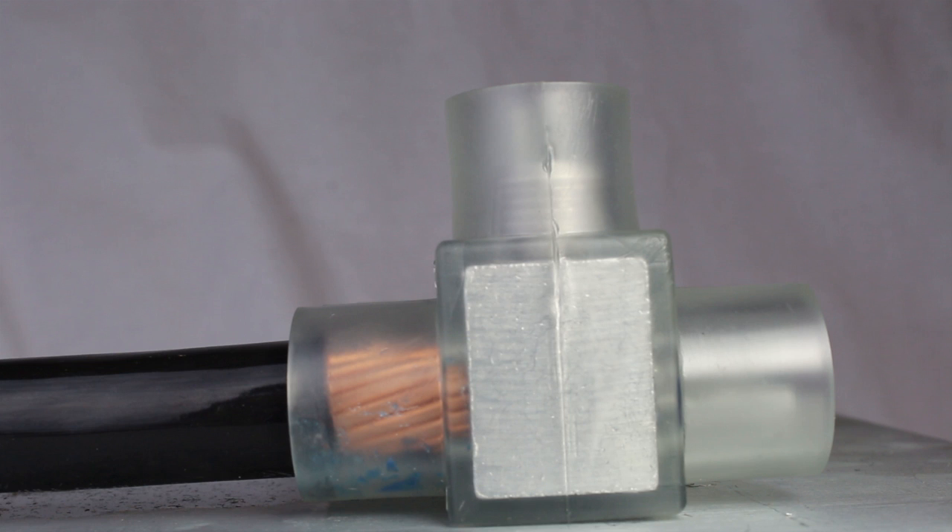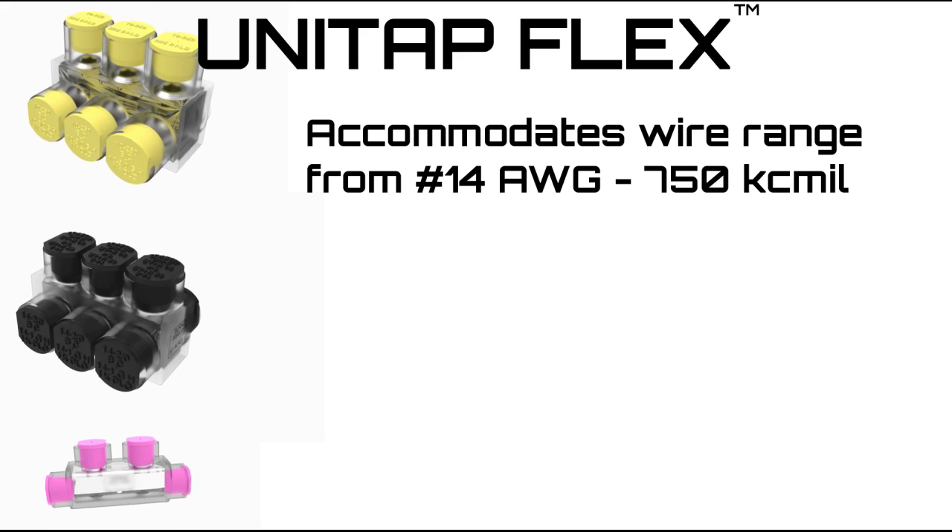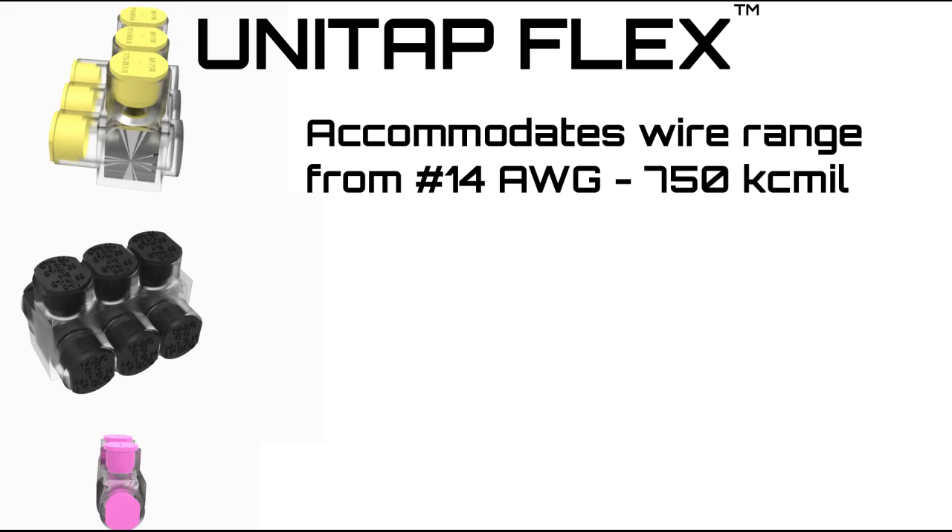Our enhanced lines of Clear UniTap connectors still allow for easy visual confirmation that the conductor is properly installed, and the insulating plastisol eliminates the need for taping. They accommodate a wire range from No. 14 AWG to 750 kcmil.